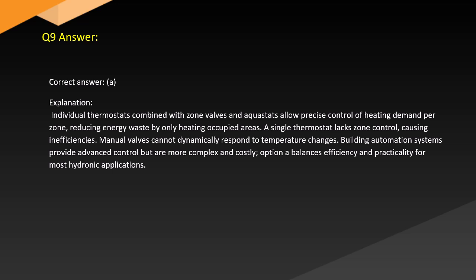Answer. Correct answer: A. Explanation. Individual thermostats combined with zone valves and aquastats allow precise control of heating demand per zone, reducing energy waste by only heating occupied areas. A single thermostat lacks zone control, causing inefficiencies. Manual valves cannot dynamically respond to temperature changes. Building automation systems provide advanced control but are more complex and costly. Option A balances efficiency and practicality for most hydronic applications.